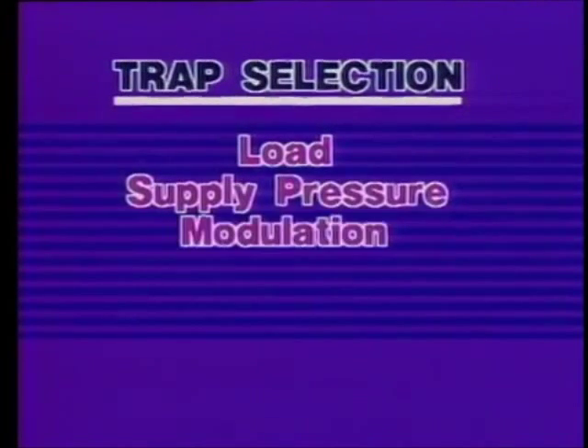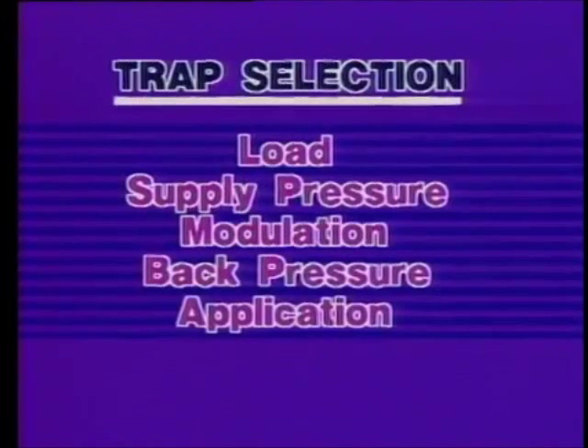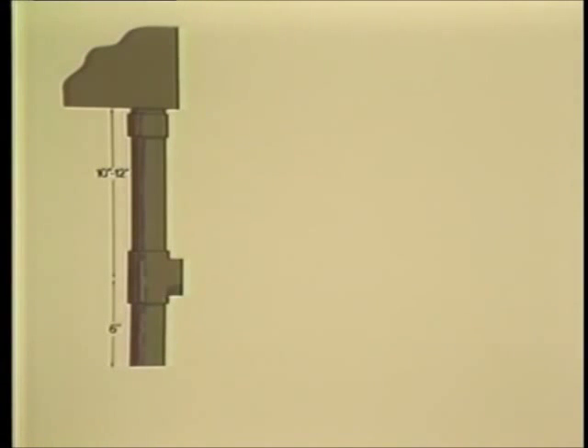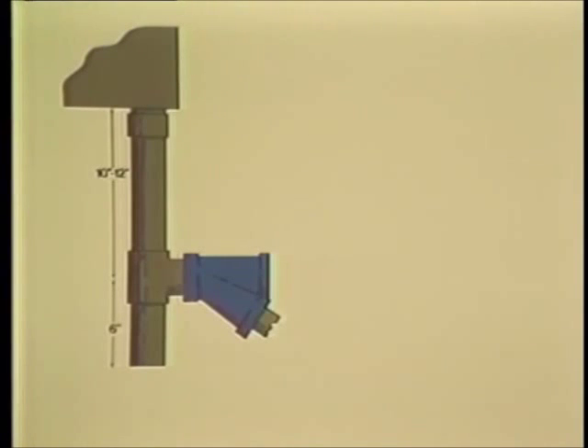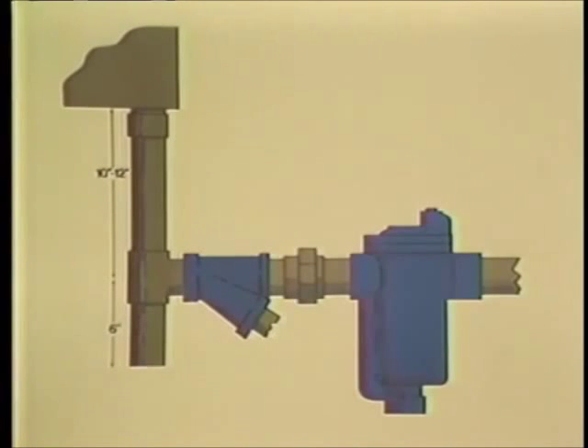Proper selection of trap type and size is based on the condensate load, steam supply pressure, pressure modulation, return line back pressure, and specific application requirements. Do not select traps on the basis of the equipment's condensate outlet size. Regardless of the type of trap selected, install a drip leg, a tee, and a 6-inch dirt leg from the condensate outlet of the process or heat exchange equipment. The drip and dirt legs should be the same size as the equipment's condensate outlet. From the side of the tee, install a strainer to protect the trap from dirt. When using mechanical traps, the drip leg should be 10 to 12 inches long. When the trap's valve is closed, the only force that moves the condensate to the trap is gravity and a slight differential pressure created by collapsing steam, so the trap should be located as close to the equipment as is practical.